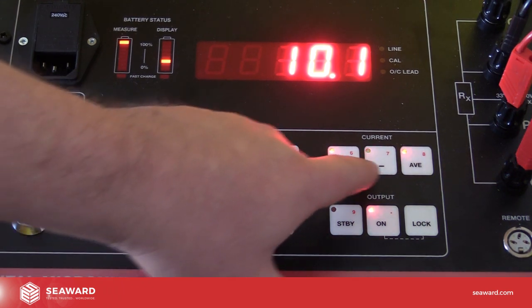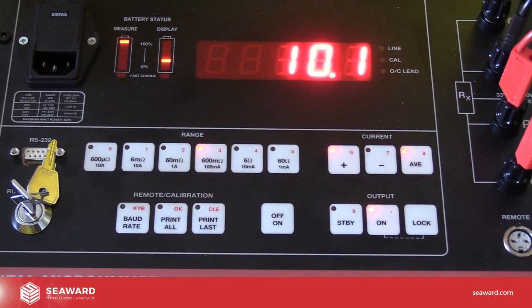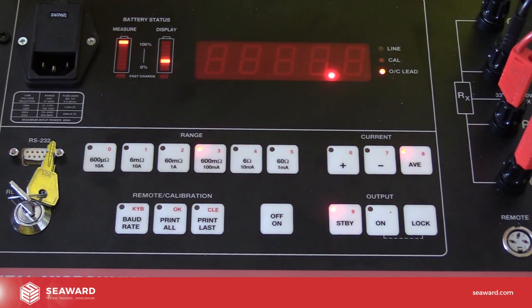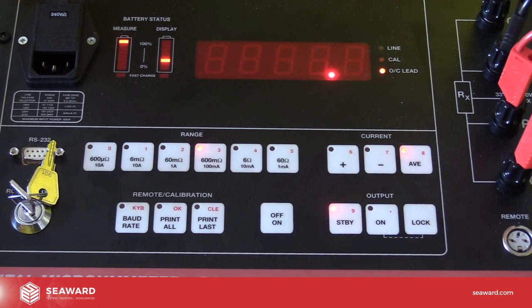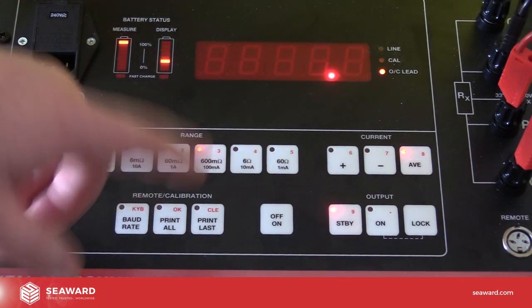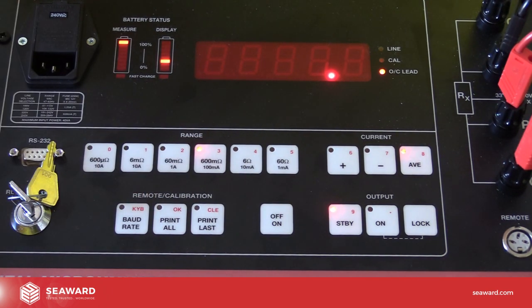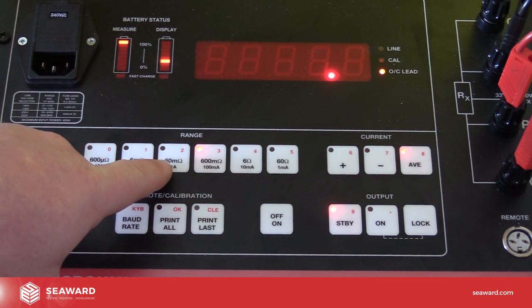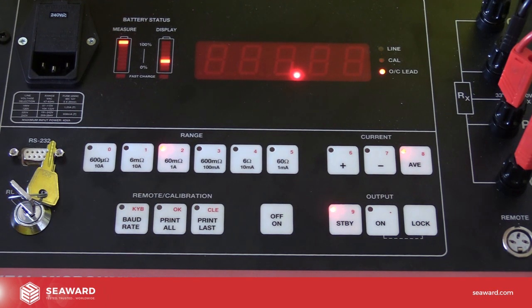You'll notice the current is moving in the positive and negative direction automatically, and every beep suggests to me that the unit is taking a measurement. For a more accurate reading, I could now look to drop the range. So we were on a 600 milliohm range, we were measuring a 10 milliohm resistance, so I could look to drop the range down to 60 milliohm. That should give me a greater resolution of measurement and ultimately a more accurate reading.